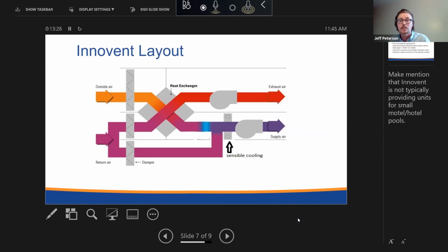Now in winter, when your outside air dew point is much lower, we modulate back on that outside air amount. We close that outdoor air damper a little bit down to around 25% of nominal. That lower dew point, we need less of that air to dehumidify the space. And so we're doing a little less heat recovery, but we're not throwing away all that energy from the pool. And that 25% is still an effective amount to maintain good indoor air quality in the colder months.